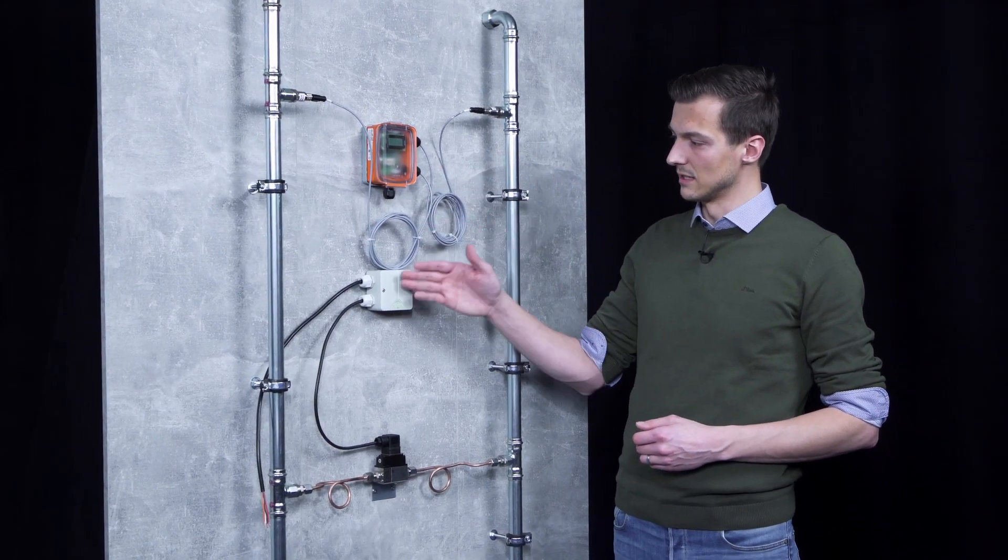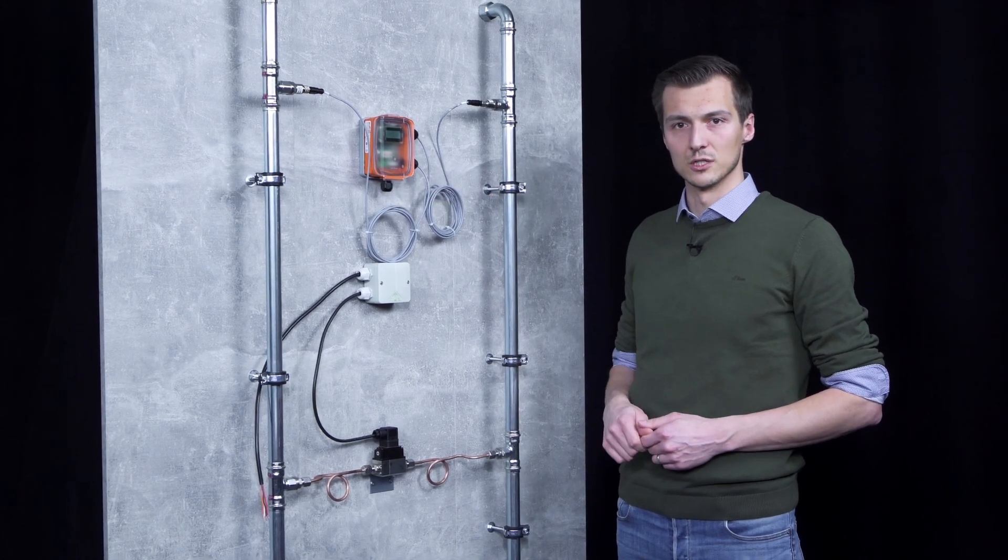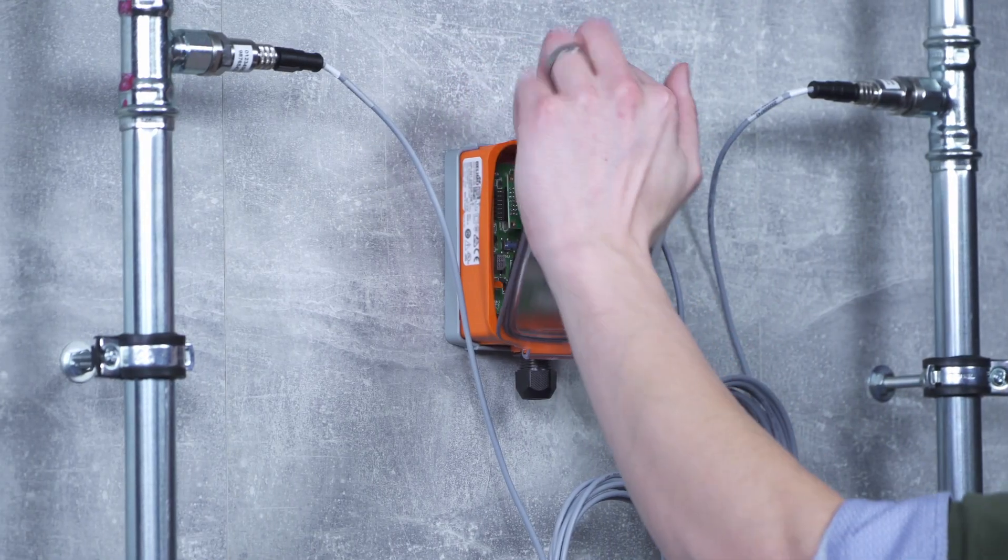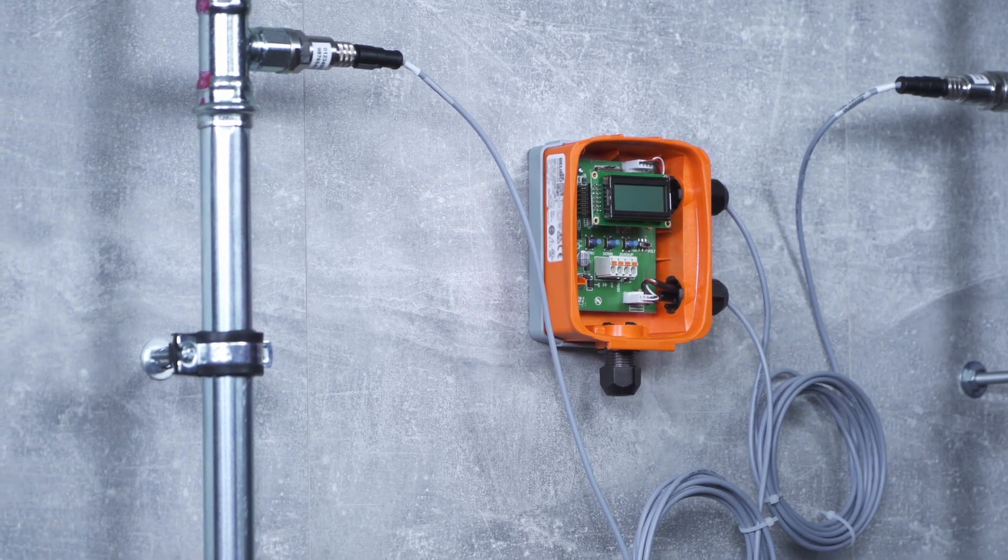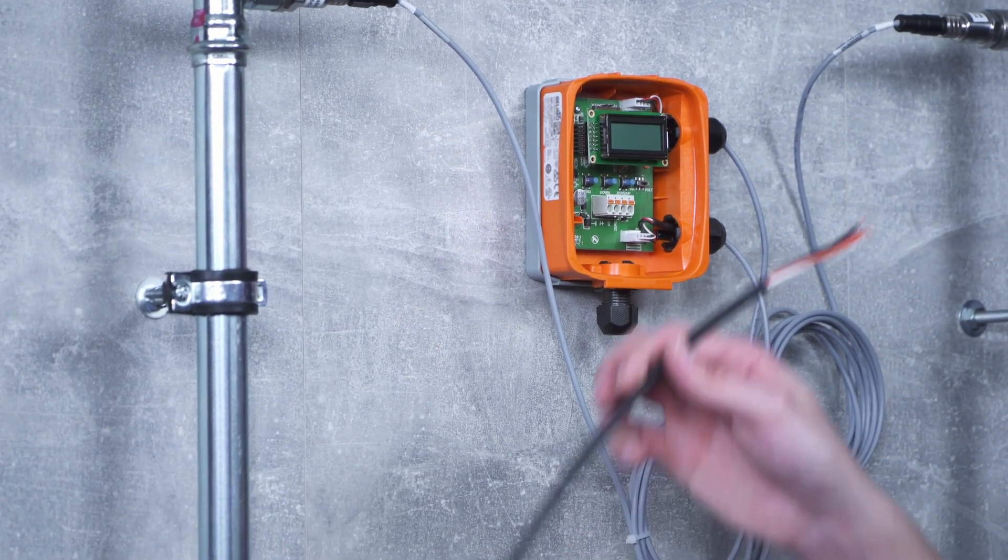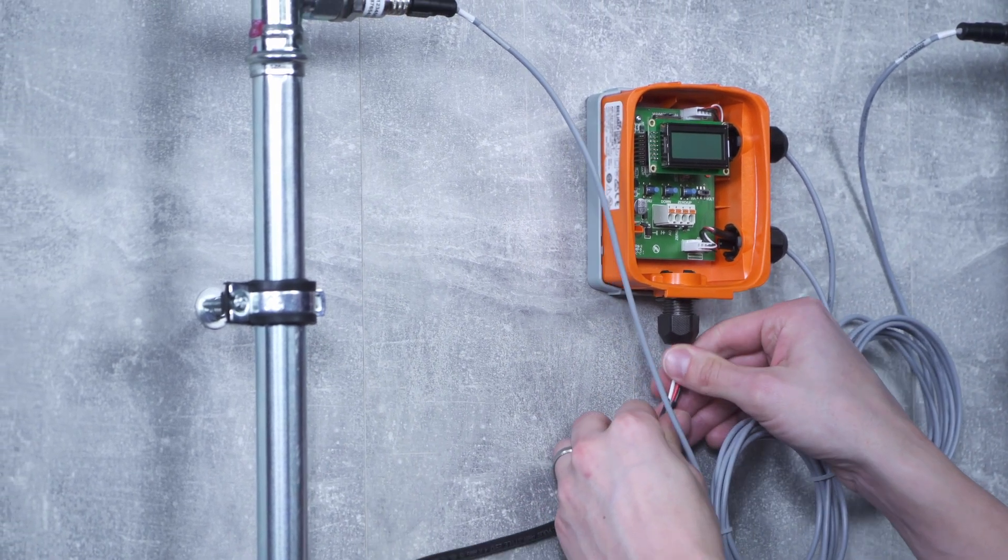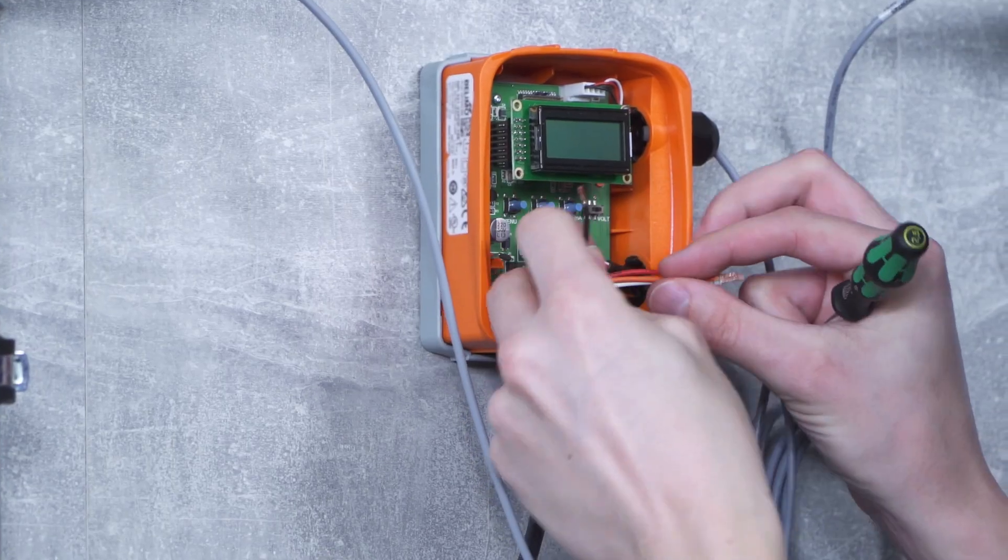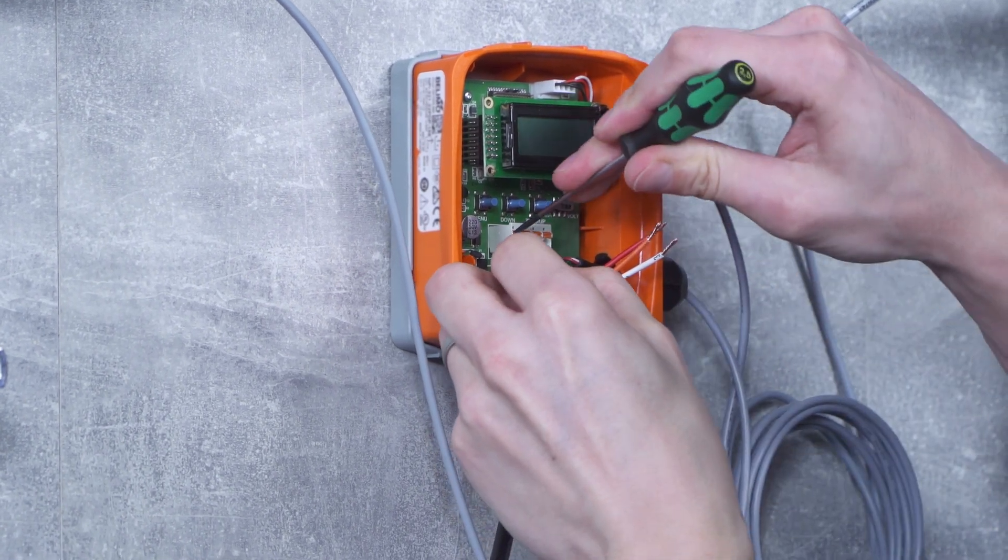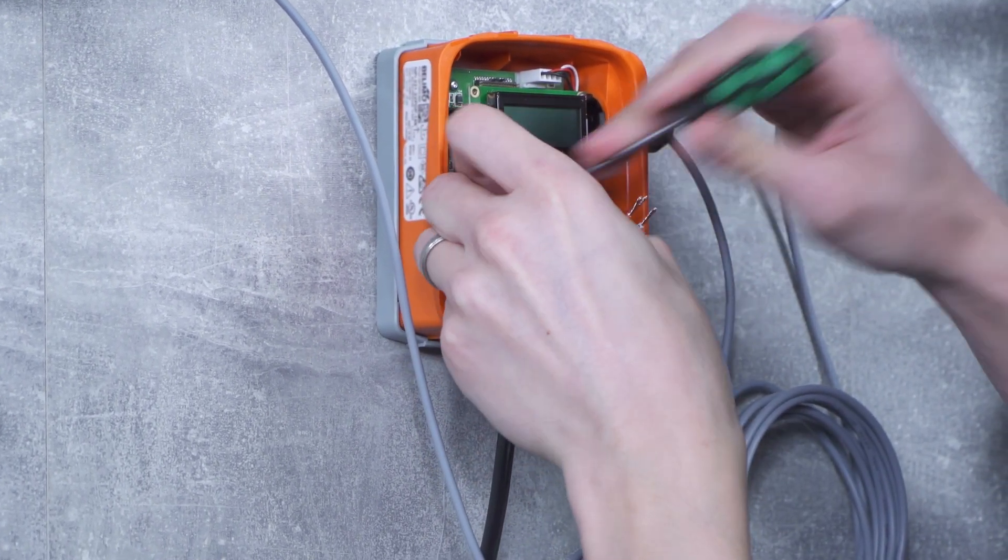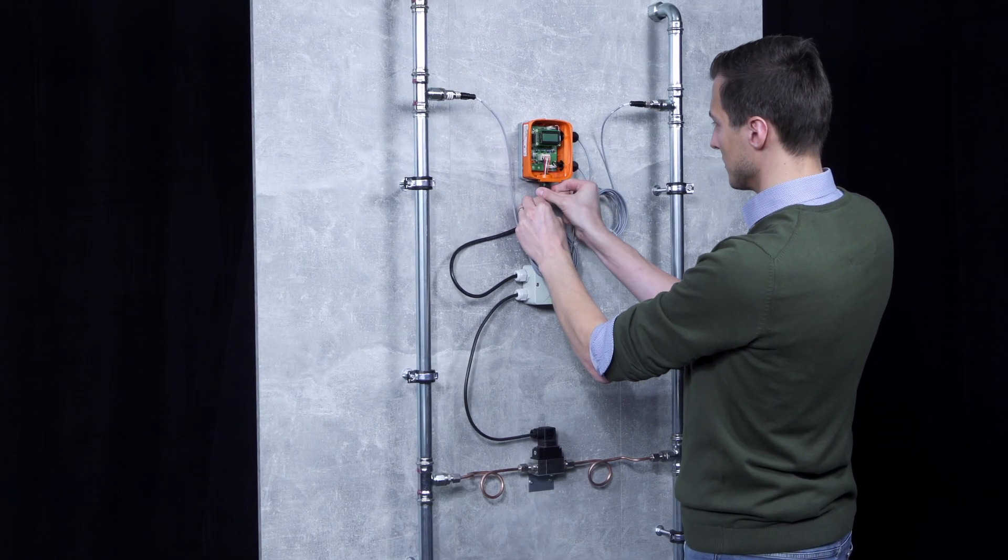The pressure transmitters are now connected to the sensor. In the next step, we will turn to the electrical installation and connect the sensor to the power supply. To do so, we first open the sensor housing and remove the cover, and then insert our connecting cable into the sensor housing. The individual cables can easily be inserted into the spring-loaded terminals with a small screwdriver. Then we tighten the strain relief and our sensor is connected.